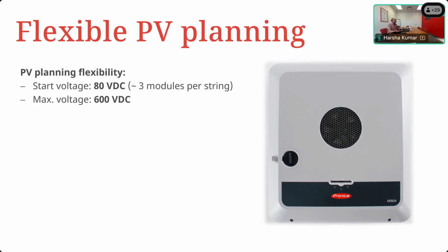Not necessarily what kind of panel. It was more about basically saying that you can start that low. The reason I say that is 3 modules per string didn't per se mean the open circuit voltage that we were referring to. We were referring to once your panels start getting hot in summer, even if I had 3 panels in series and the open circuit voltage for each of those was, let's say, 42 volts, it should be approximately 120 volts. But once you start drawing power from them, the MPP voltage is usually about 70 to 80% of that open circuit voltage, which comes down to 80 volts. That's where I was getting to, not so much how many cells we have in each module.